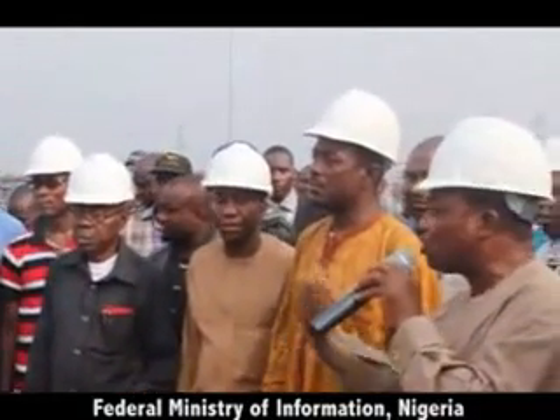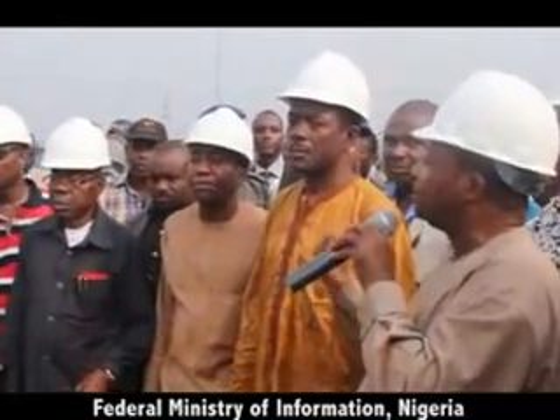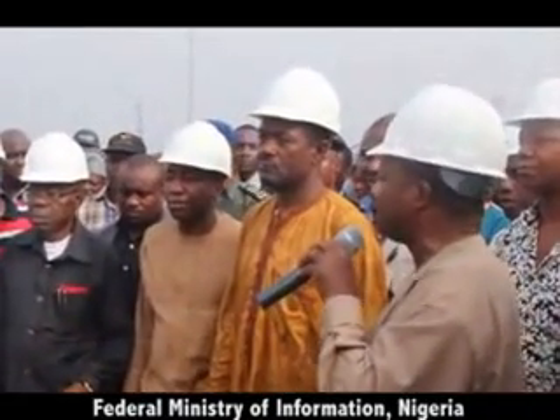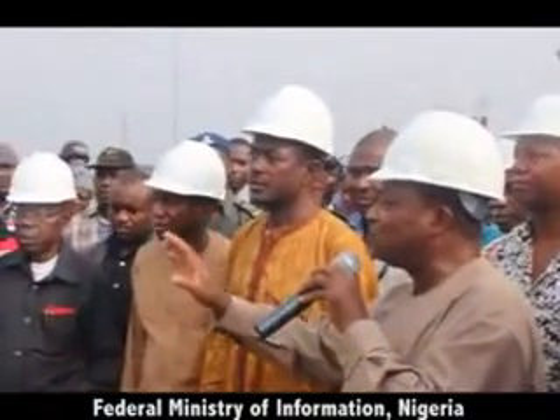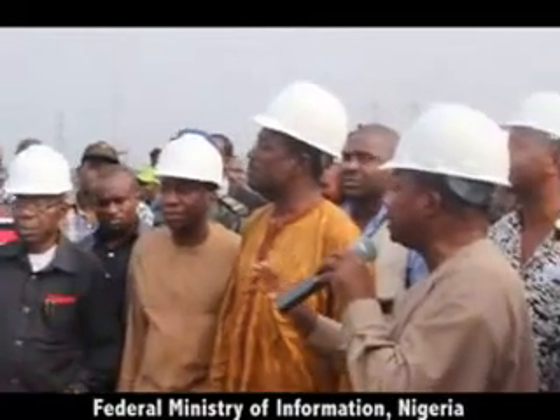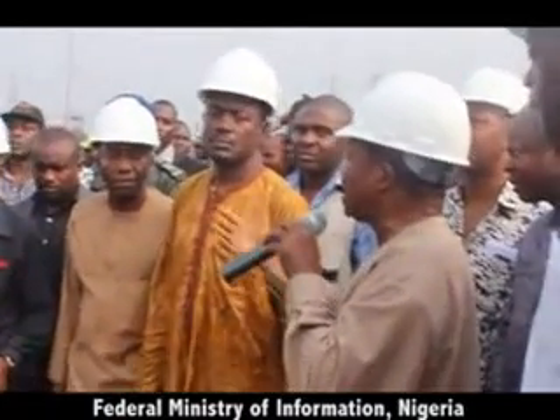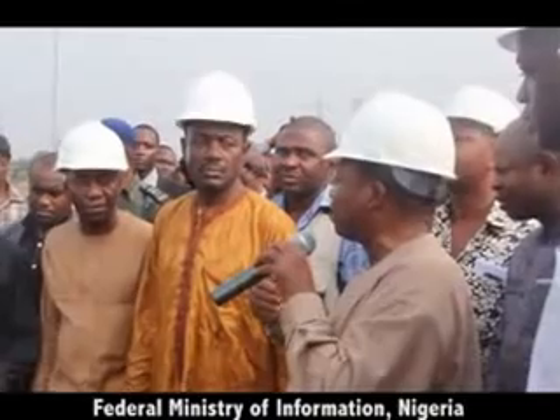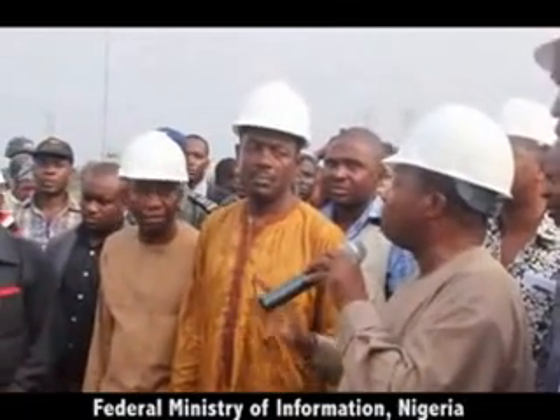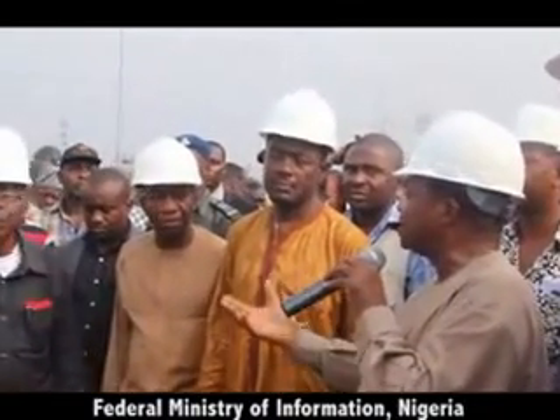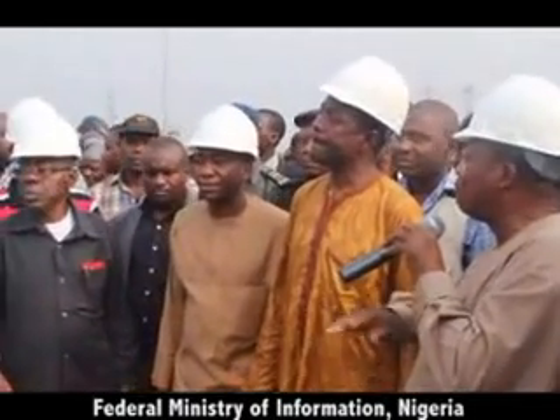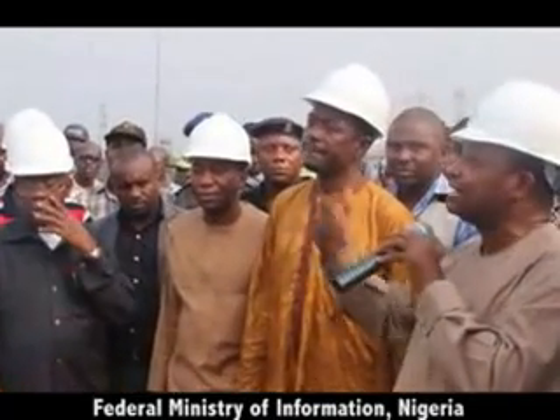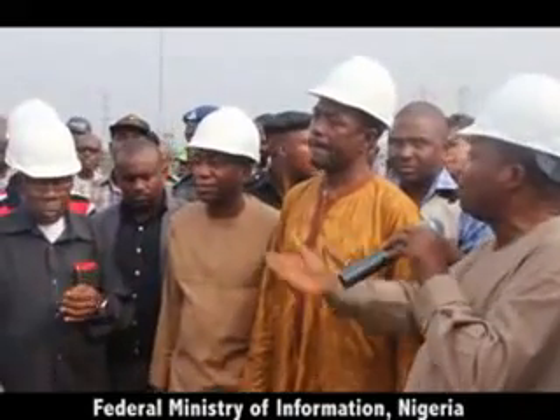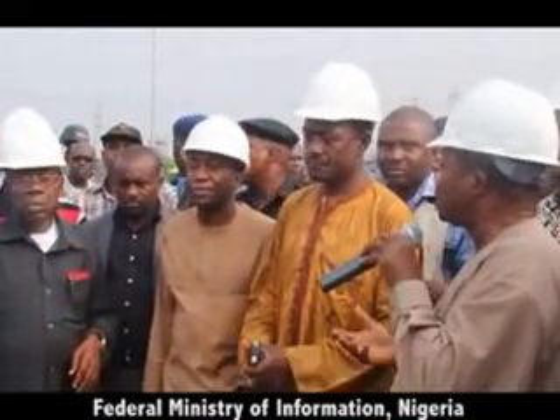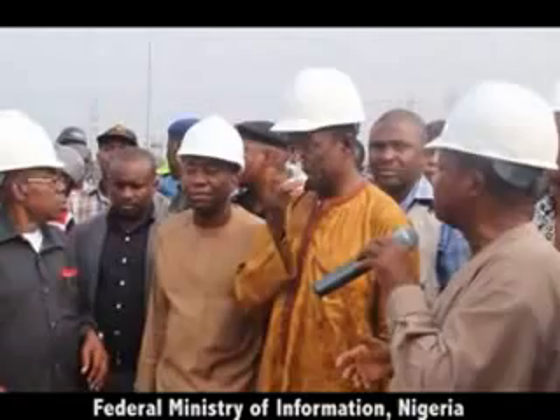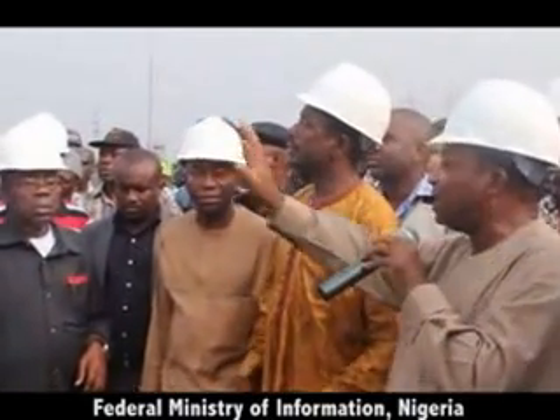The gas turbine will first be energized before the steam turbines, and construction of that is ongoing. This is one of the few plants in Nigeria able to start by itself without importing power from the national grid. If there's no power, we can still start, black start, and then start the bigger machines to give power to others in case of a national grid collapse. That's the black start facility.